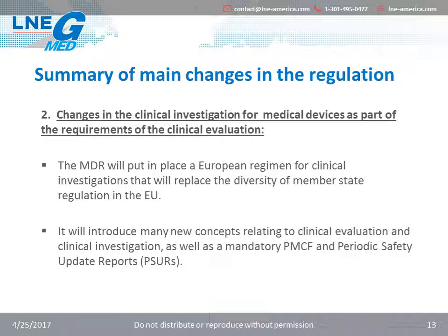The second change is in the clinical investigation for medical devices as part of the requirements of the clinical evaluation. The MDR will put in place a European regime for clinical investigations that will replace the diversity of member state regulation in the EU. Also, it will introduce many new concepts relating to clinical evaluation and clinical investigations, as well as a mandatory post-market clinical follow-up and periodic safety update reports.